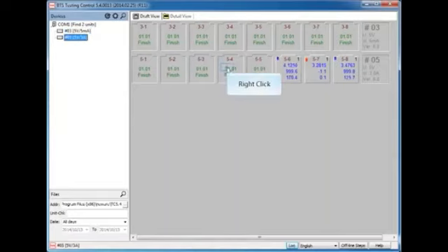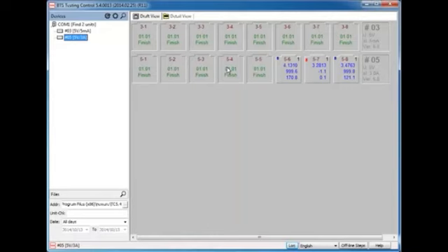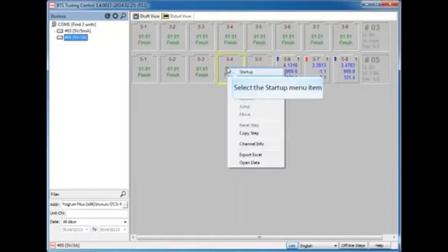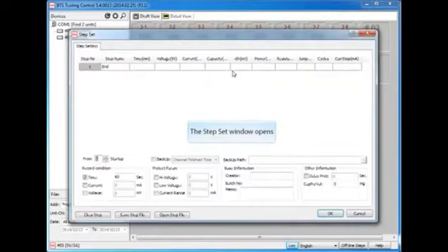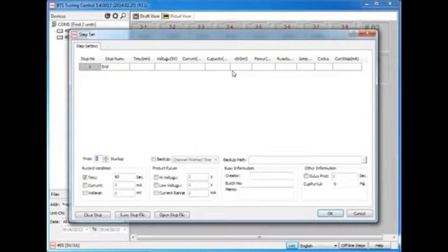Right-click on any of the channels you want to start up a test. Select Startup from the pop-up menu, and the Step Set window shows up. In here you can choose testing steps and set up all the conditions according to the battery test you want to do.